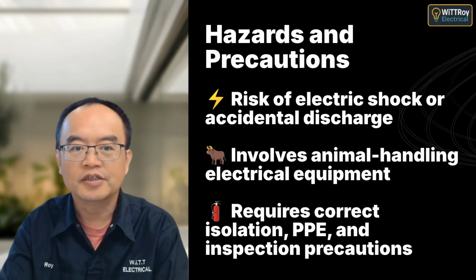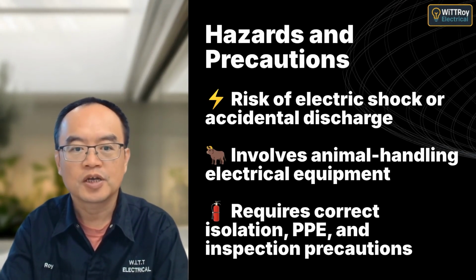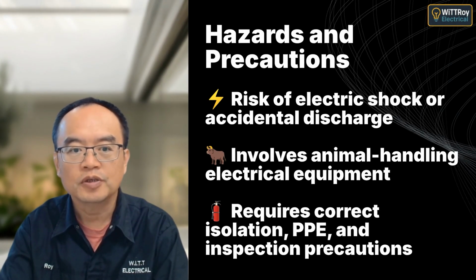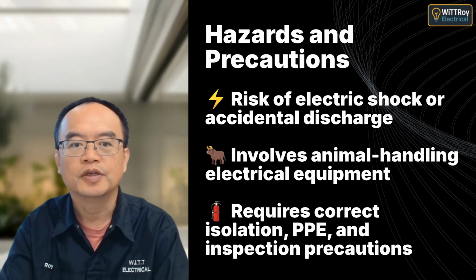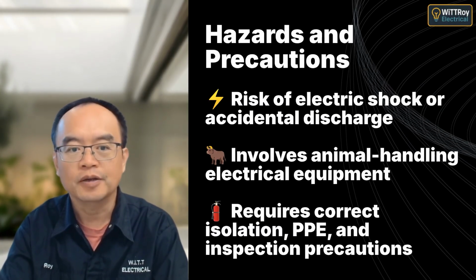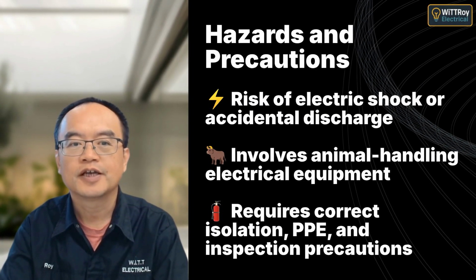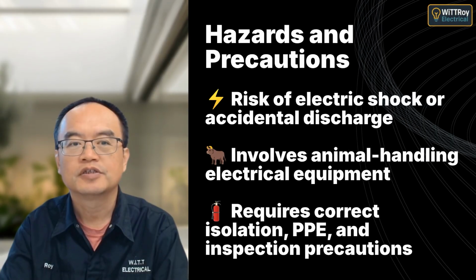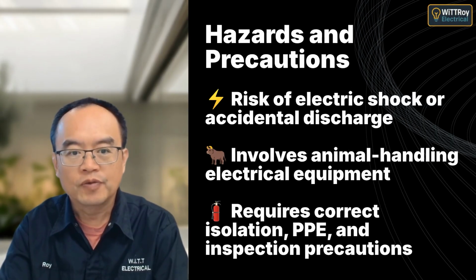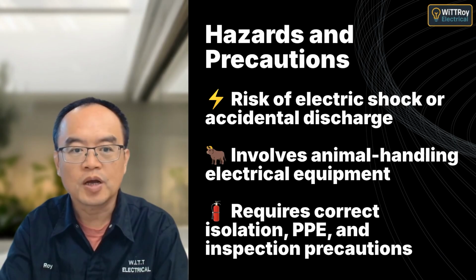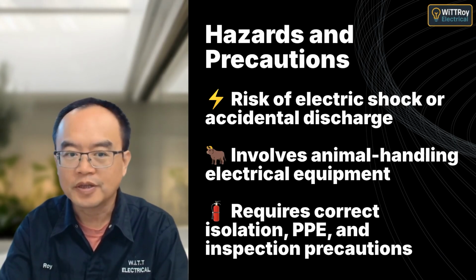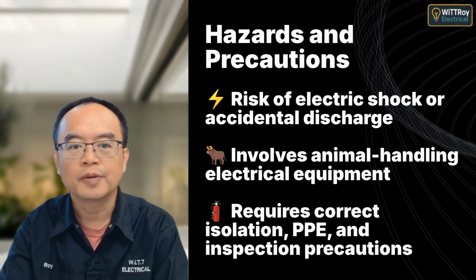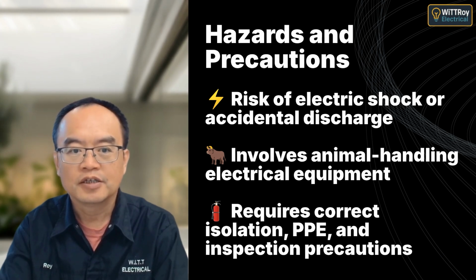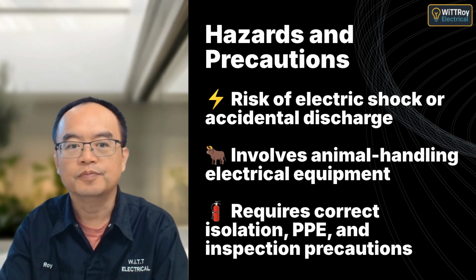According to NZS 6116 2006 Clause 4.4.2, all plant and equipment, including animal stunning gear, must be inspected before use and safely isolated during any checks or servicing. These devices may involve high voltage and operate in wet or harsh environments. Inspectors must control the risks of shock, mechanical damage, or accidental activation by following strict isolation and inspection procedures.